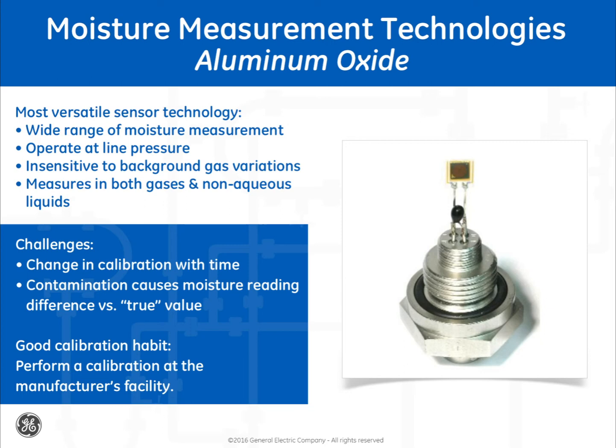Due to their physics, metal oxide sensors change in calibration with time. Their installation in erosive or corrosive processes may accelerate this change. Contamination can make the sensor look like it is out of calibration. One can use portable analyzers and the verification techniques above to check the performance of the measurement system. Best practice is to perform calibrations at the manufacturer's facility on a regular basis.